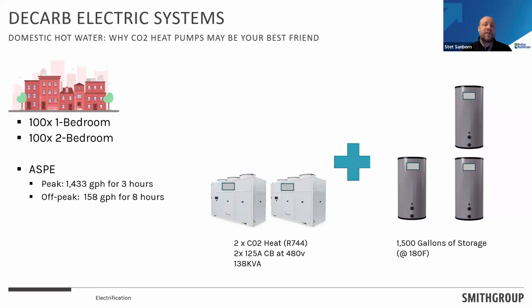A typical CO2 heat pump is going to make 165 to 180 degree water when it's really happy, even when it might be 12 degrees below zero outside. It loves cold climate hot water production. Because I can make really hot water, the tank size and volume can be much smaller.